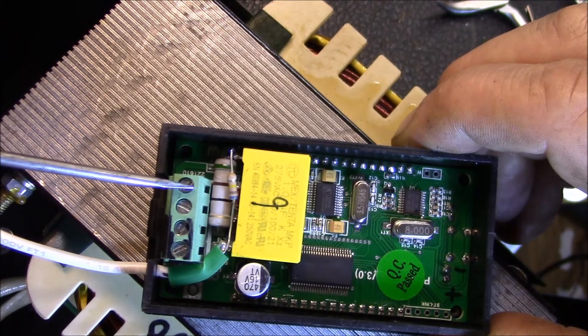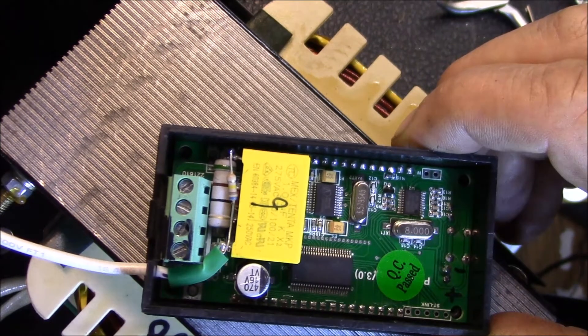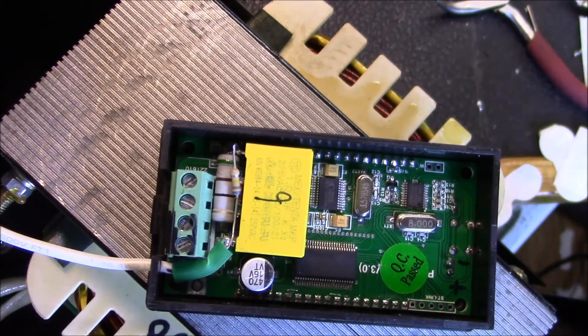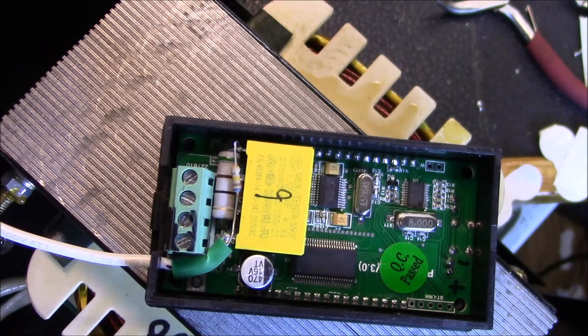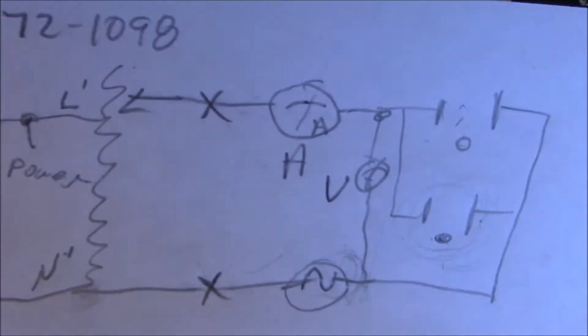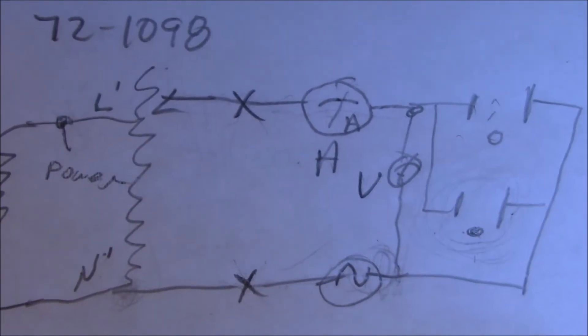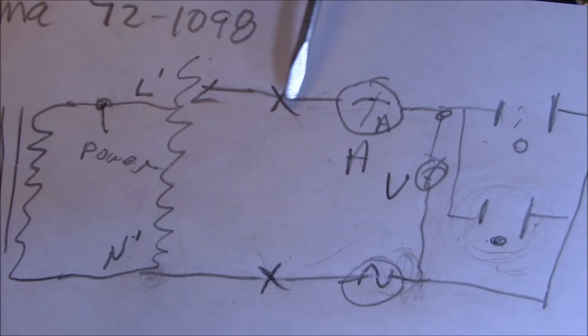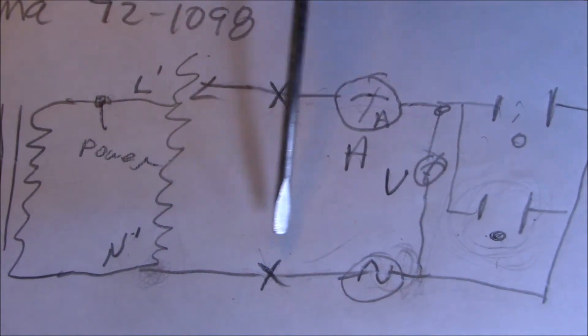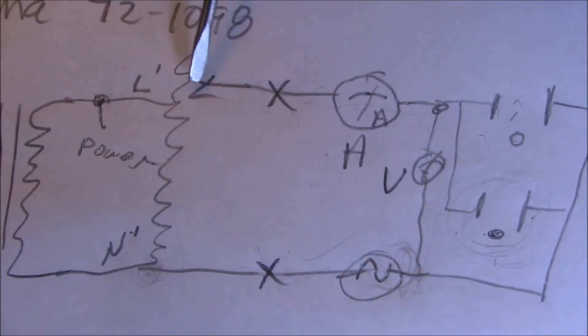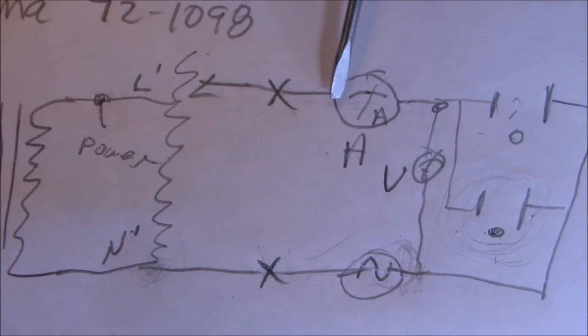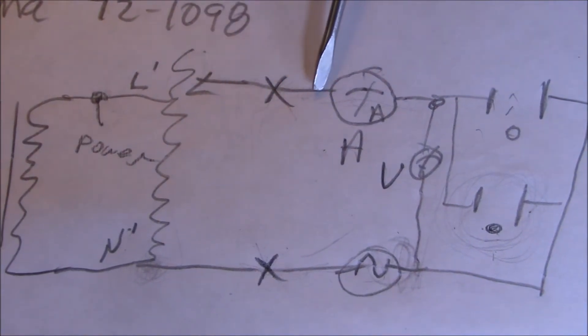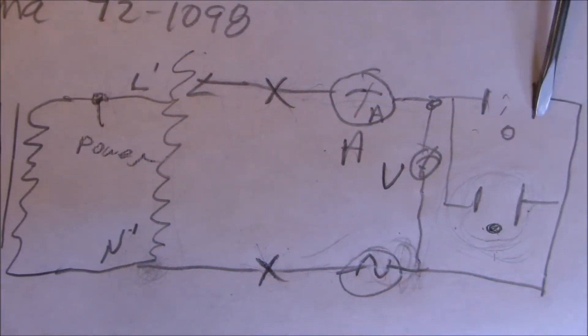The way to think about it—if we can look at my little diagram—the way you wire this meter in is: here's my AC power supply, and this is the wire that comes off of the variable output of the variac, goes to the two outlets that are on the front of the supply, and then flows back to the variac. But this could be anything. The idea is you just cut the wire that's feeding your load and you cut the wire that's coming back from the load.